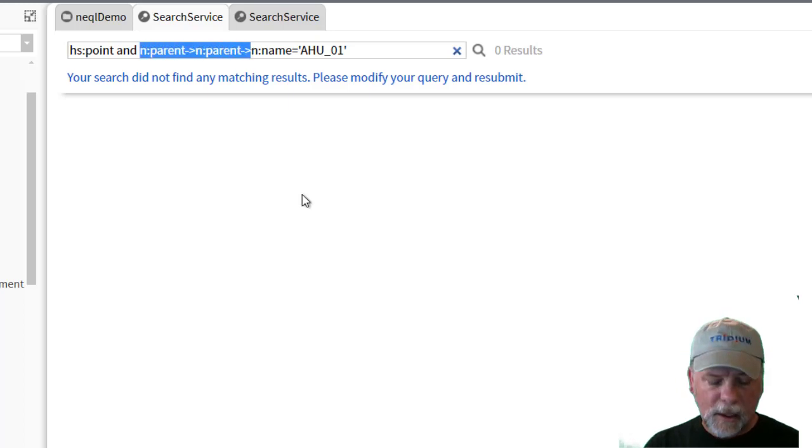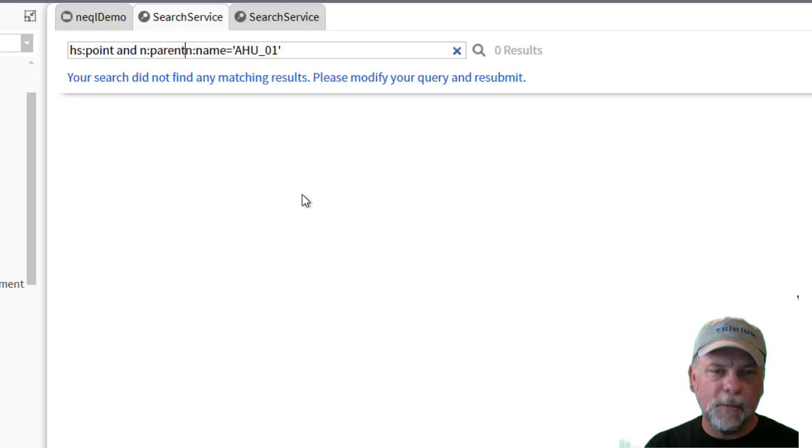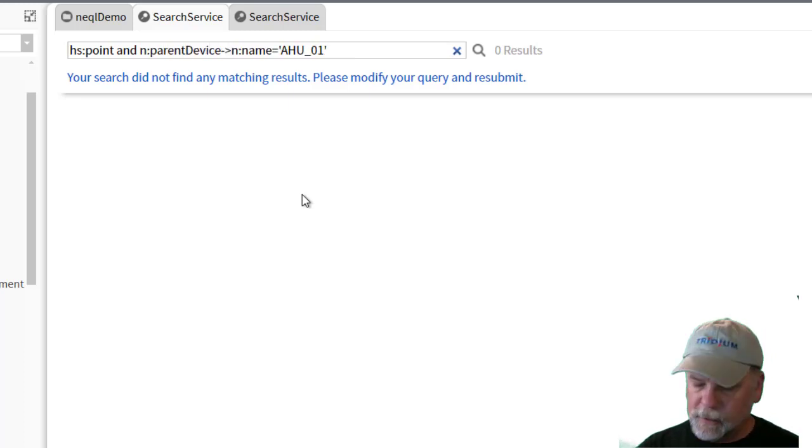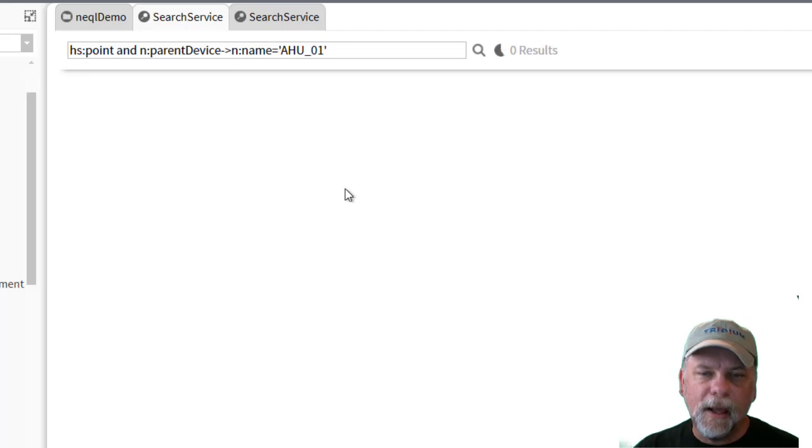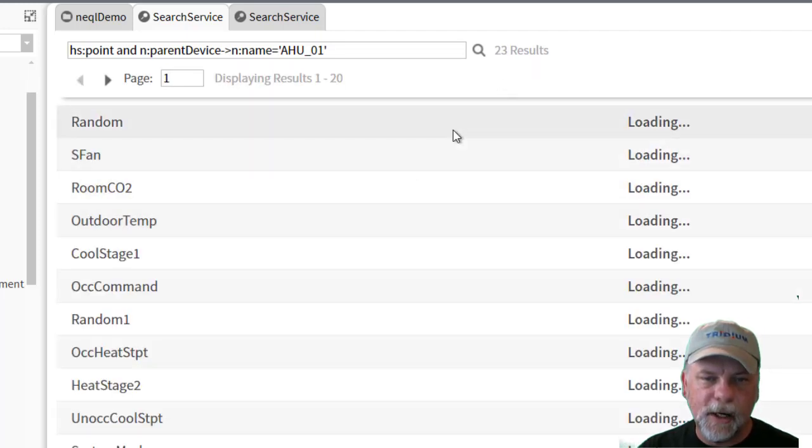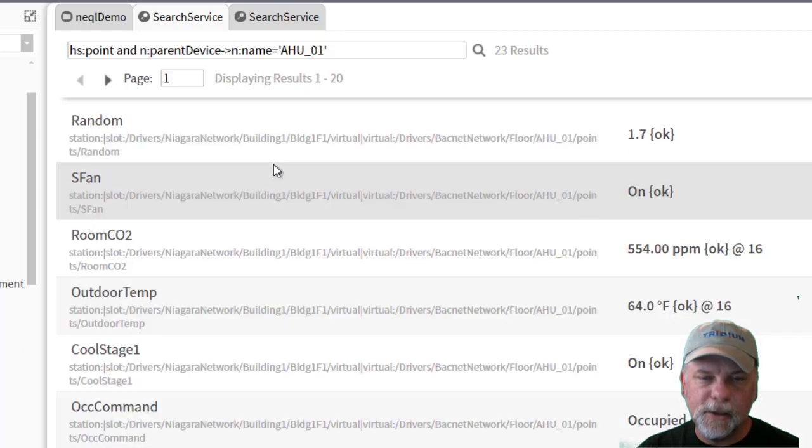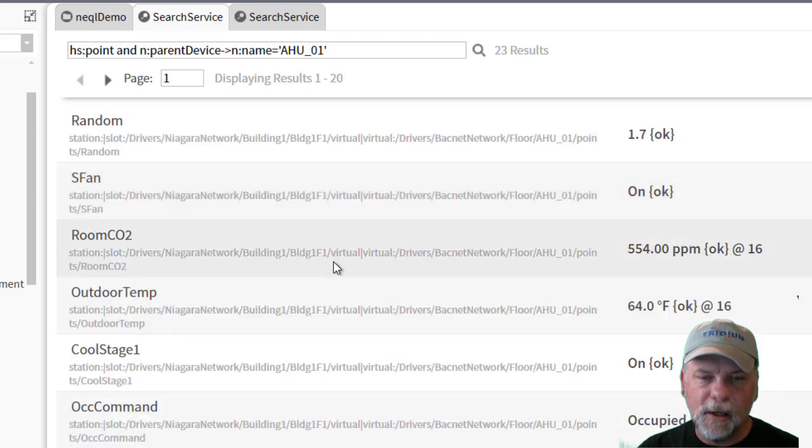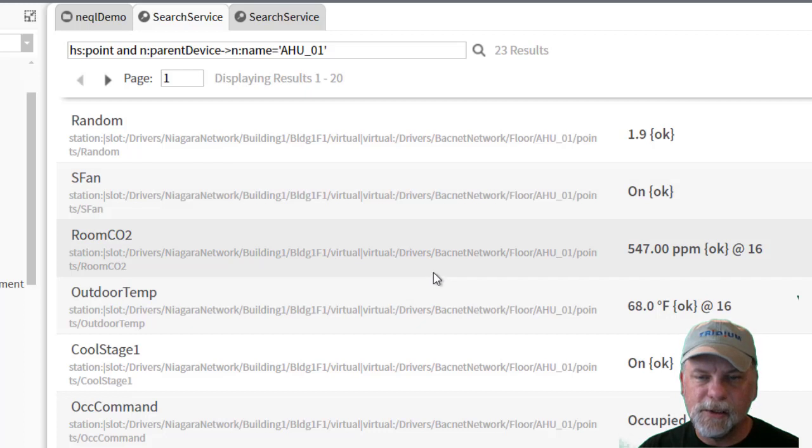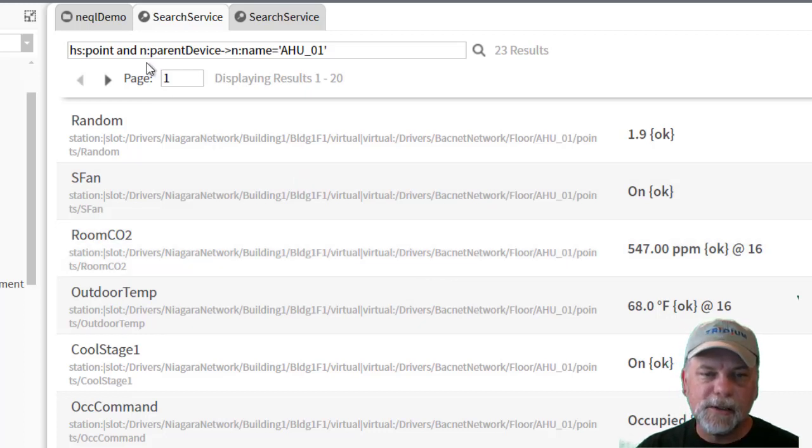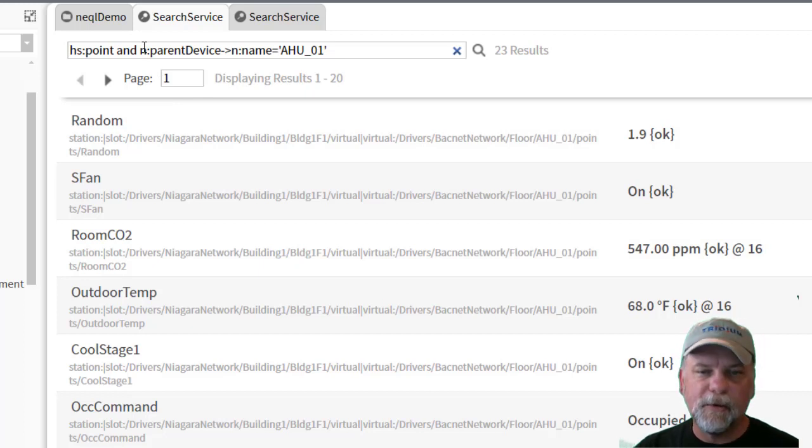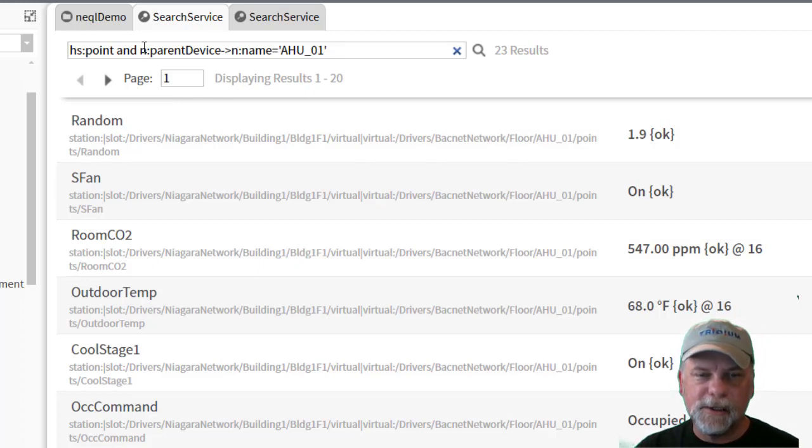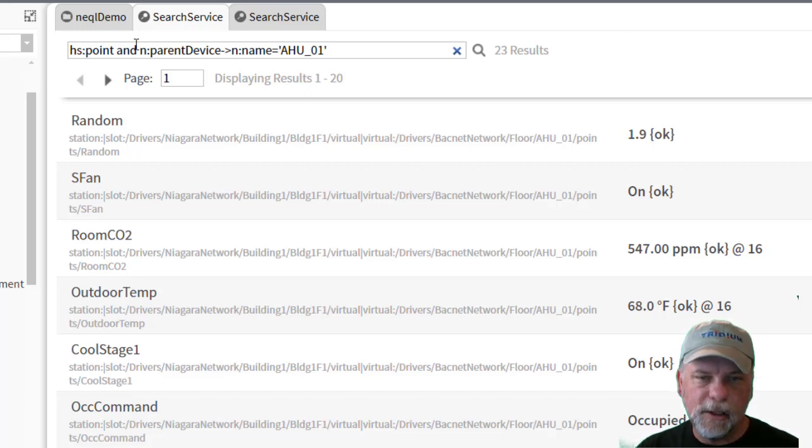So I really can't use the parent parent because that component, the point device extension, hasn't been indexed in the system database. I should however be able to use n colon parent device outbound relation and check the name, and that should find the 23 points under air handler one. And this will be using the virtual org space through the virtual gateway to display the point values and potentially the graphics. So it is possible to still use these same queries at the supervisor level, but you have to understand what may or may not be indexed by the system database and possibly adjust your indexing queries.